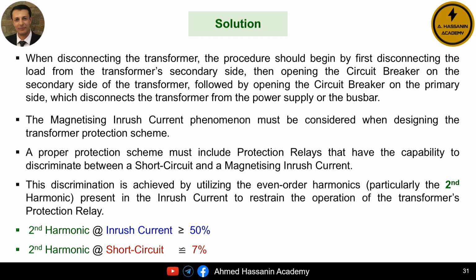Thus, we can take advantage of this large percentage of second harmonic and distinguish whether the large current that occurs in the transformer is magnetizing inrush current or a short circuit current due to a fault. This distinction is a feature available in the differential protection relay of the transformer. Therefore, we can use this discrimination feature to prevent the differential protection relay from tripping in the event of magnetizing inrush current. As we said, all of this depends on the percentage of the second harmonic present in the large current when the transformer is connected to the service.